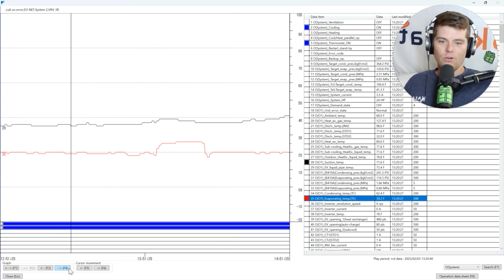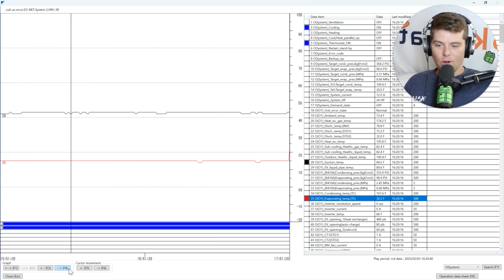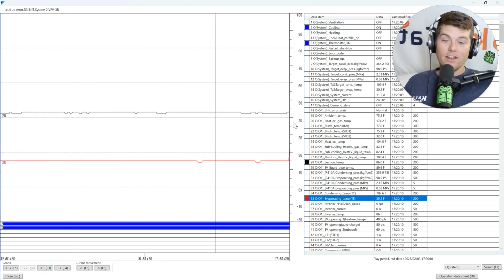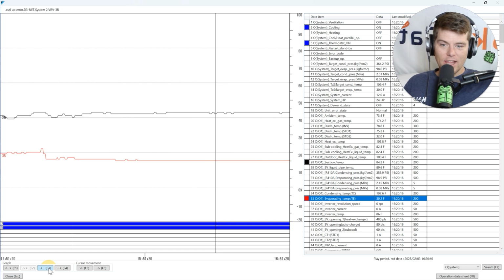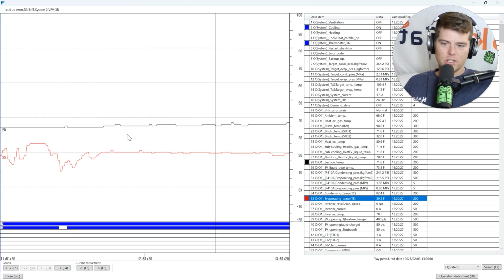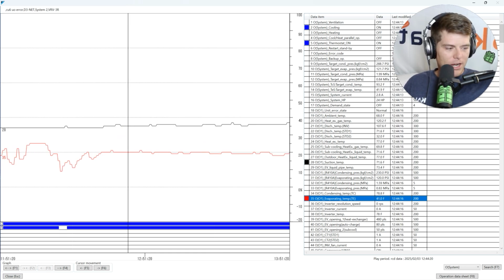So we go and we scroll and we scroll and we scroll. And you'll notice at the end of my data snippet, wow, these lines are actually pretty far apart. They've gotten two gray lines apart. Now we're at a suction superheat of what? It looks like we're 86 degrees and 30. That's 56 degree suction superheat. That is very high. Okay. Notice how 6 hours later, it gets to the point where it's noticeable. And why is that? Oh, let's break it out. Let's break it out. Okay.